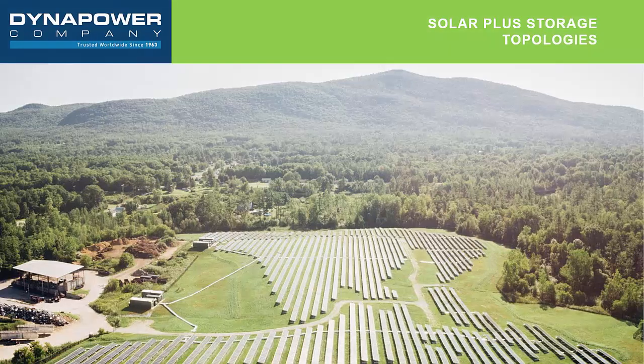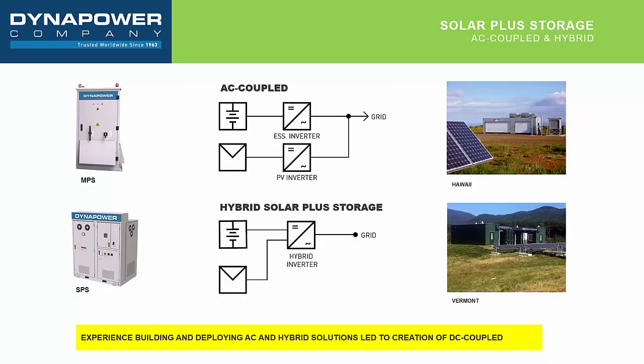So let's go through this really quickly. Just what are these topologies? What are these options that we have when we talk about coupling storage plus solar? The traditional methodology is the AC coupled topology. In the AC coupled system, you have your PV inverter, you have your storage inverter, and they meet up on the AC bus. Typically, they meet up on the AC medium voltage bus where they are tied together in front of the point of interconnection.